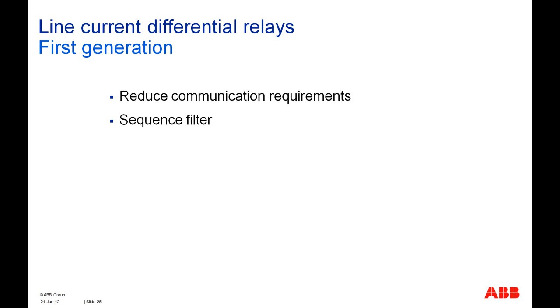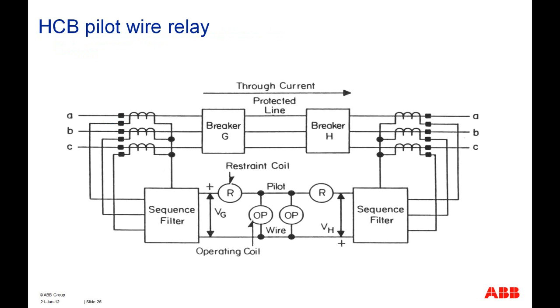Now let's talk about how many types of line current differential relays we have, or we had. So some of you might remember those pilot wire differential relays. So those were the first generation of line current differential relays, and those were used not for very long lines, but for short lines or medium lines. So let's talk about what the pilot wire line differential relay is. HCB is the relay in the ABB product portfolio to cover the pilot wire line differential protection relay.